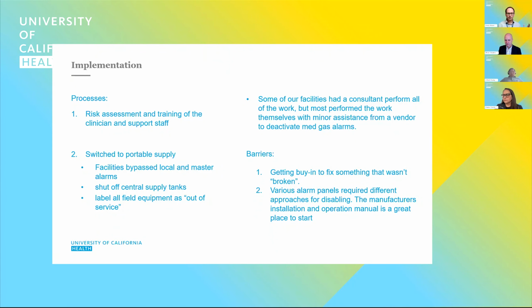While you're establishing that distributed supply, facilities can be doing their legwork to determine how to disable your local and central med gas alarms. That's probably one of the biggest hurdles. I can't stress enough: start by finding the manual for each of your alarm panels. Oftentimes that's all it takes — just going through the instructions will often tell you step by step how to disable those alarms.